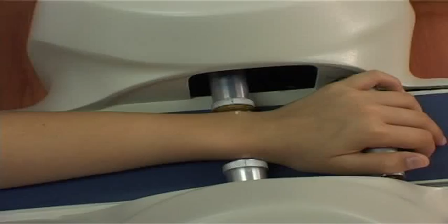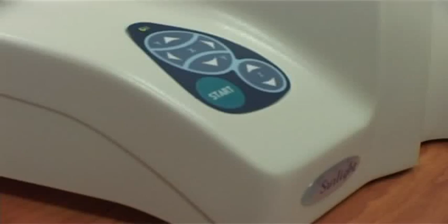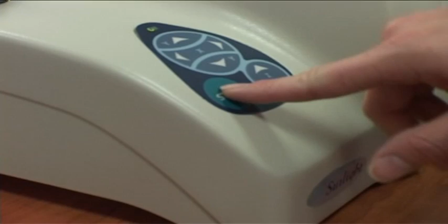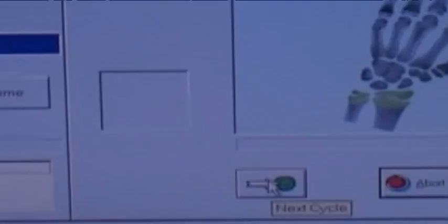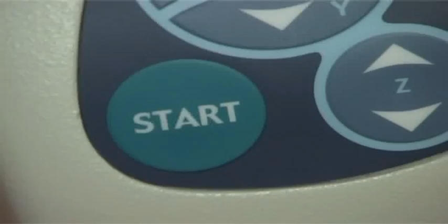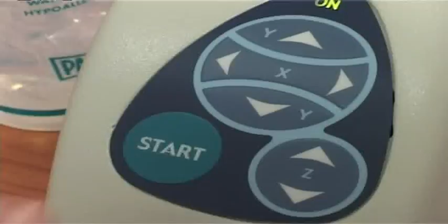The operator then detaches the transducers from the skin of the patient. Next, the operator presses the Start button on the measurement unit keypad, or clicks the Next Cycle button on the screen to start the next cycle. This process is repeated until the Next Cycle button is disabled. This process can take up to 11 cycles.